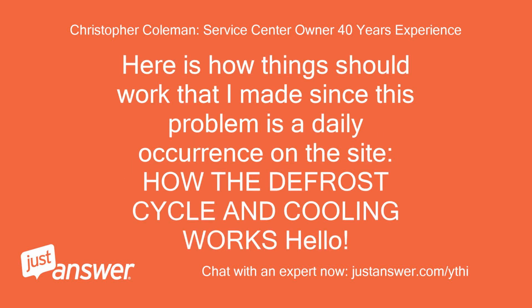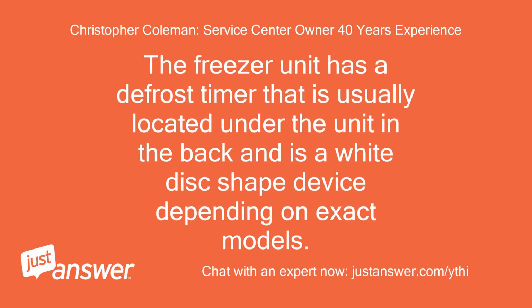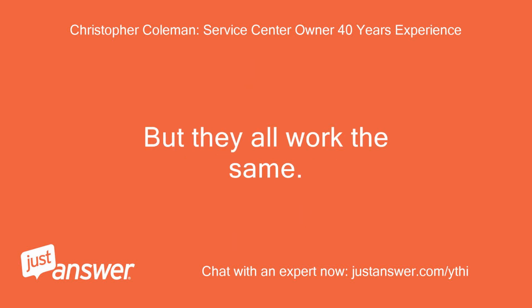Here is how things should work that I made, since this problem is a daily occurrence on the site, how the defrost cycle and cooling works. Here is how all freezers/fridges/and coolers work. The freezer unit has a defrost timer that is usually located under the unit in the back and is a white disc-shaped device depending on exact models. But they all work the same.